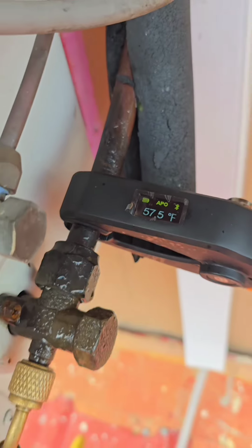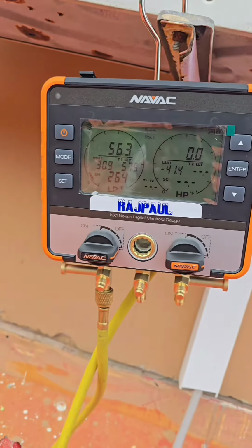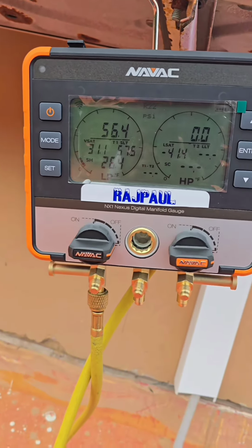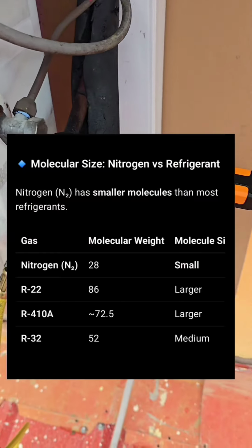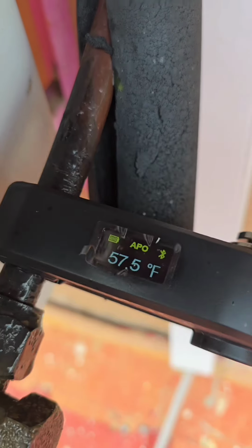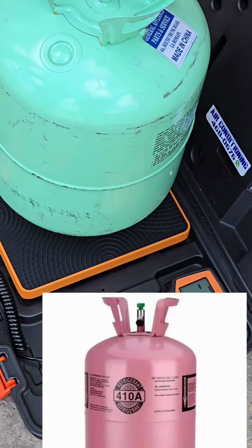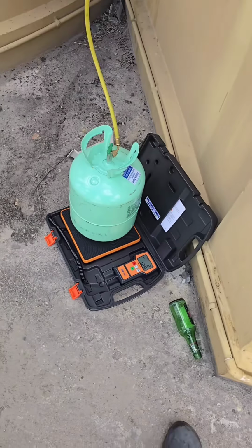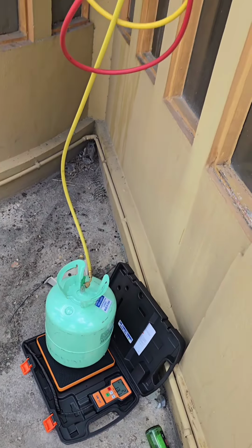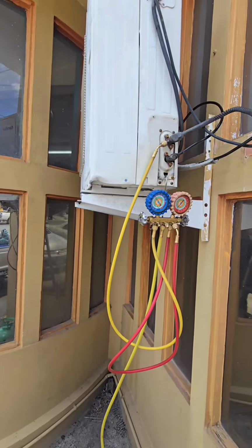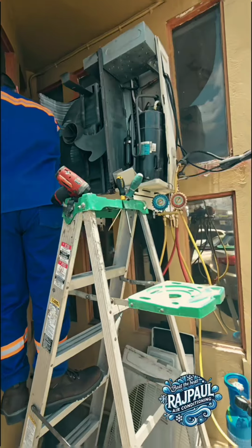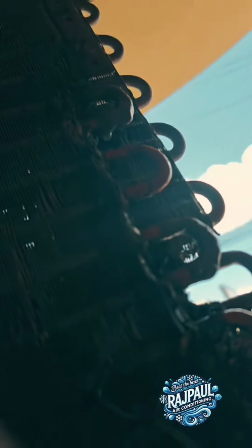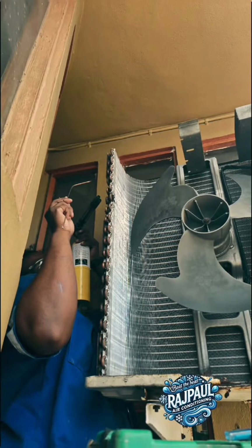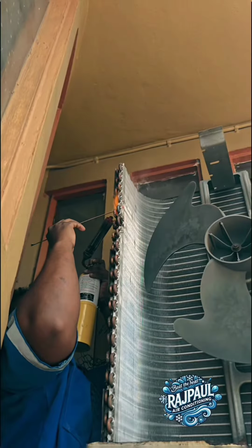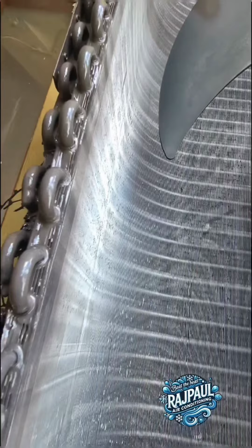Number two would be its molecular size. Meaning nitrogen is two times smaller of a molecule than 410A. So sometimes you'll be looking for a leak with gas like before, as I said, and you're not finding it. And boom, as you put in the nitrogen, same place, you see it. Because the molecule is smaller and it will pass through that hole or that leak quicker or easier.